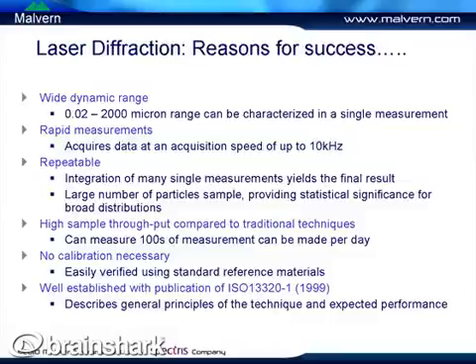Laser diffraction measurements are very repeatable, because even at lower speed measurements where we get a result once a second, we're integrating many snapshots to the detector to give us the final result, so we're collecting an awful lot of data. As we measure the samples for a number of seconds, we're sampling a large number of particles, and that gives us statistical significance even for broader distributions.